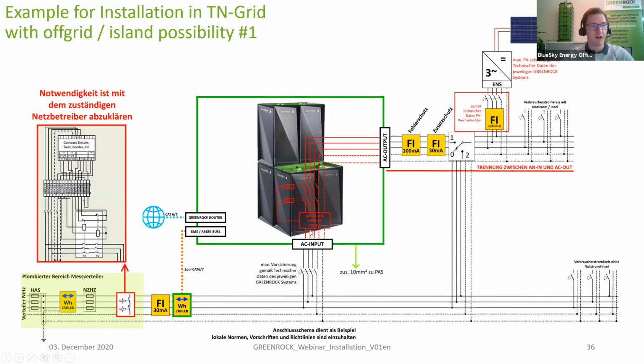But if you now have a grid failure, the system again stays active. You will have a grid on the AC out, you will have a voltage, you will have a frequency. So that also means this inverter can connect to a grid. It will stay active, it will supply the loads, and it will also charge the batteries. But please always be aware of some maximum values which are important here. This is also part of our technical data sheet, so that you can see which system is able to apply which PV inverter on the AC output side. So please do not overstress a system with a too powerful PV inverter on this connection. For example, on a one-phase system, the maximum connection here is 3 kilowatts. So really be aware of that.